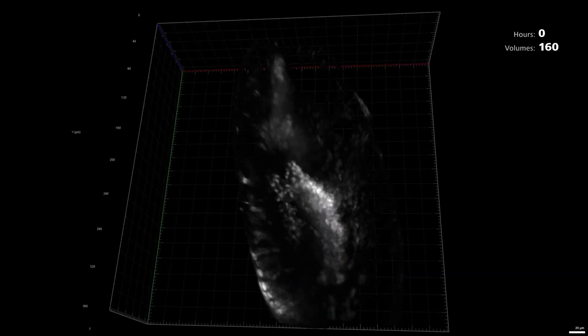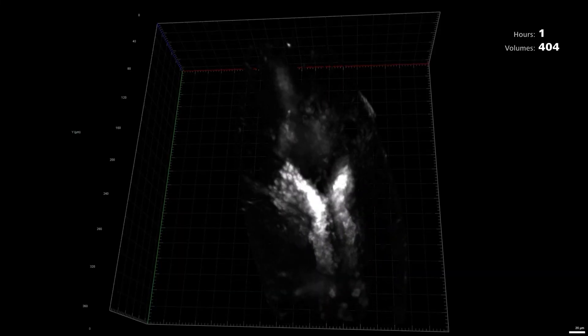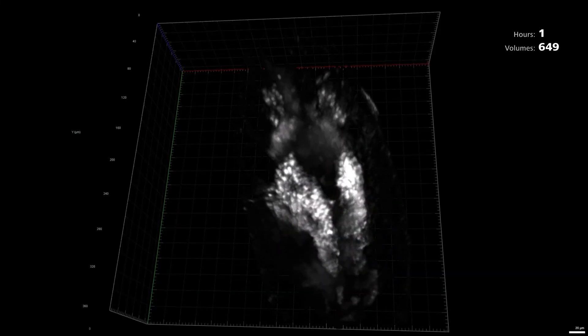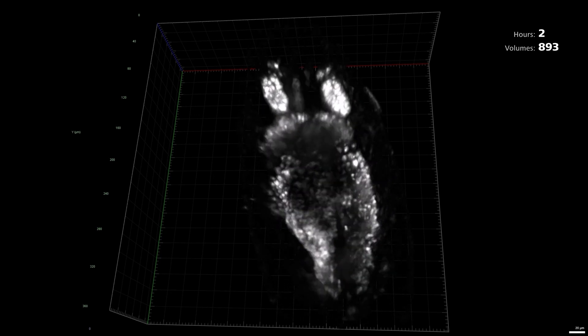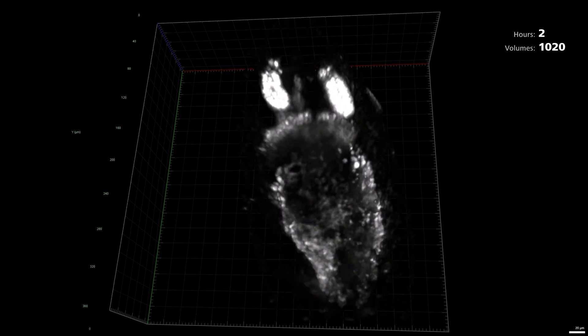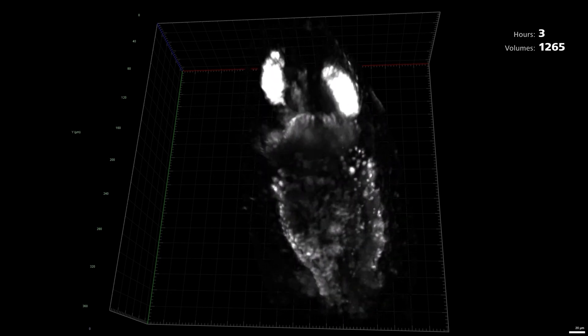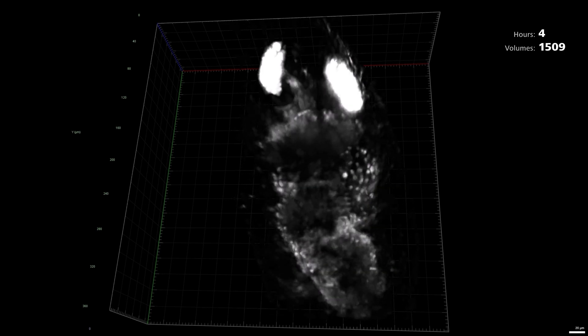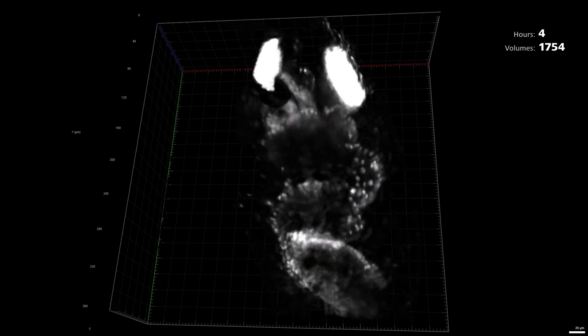What's cool is that this instantaneous volume acquisition is also really gentle for imaging live samples. Here we can see an example with the Drosophila gut development — we took an image every 10 seconds for 5 hours straight for this sample, and we didn't see any evidence of phototoxicity. This means we can really use the fast volume acquisition without harming the sample at the same time.